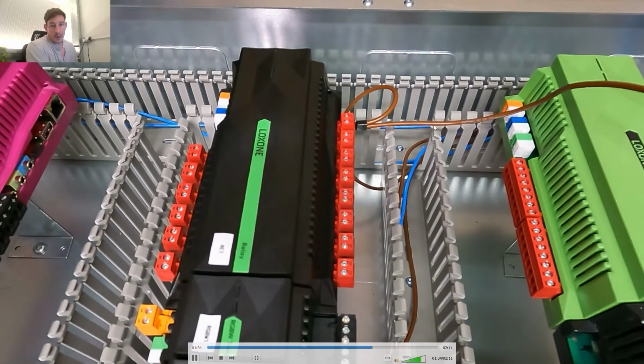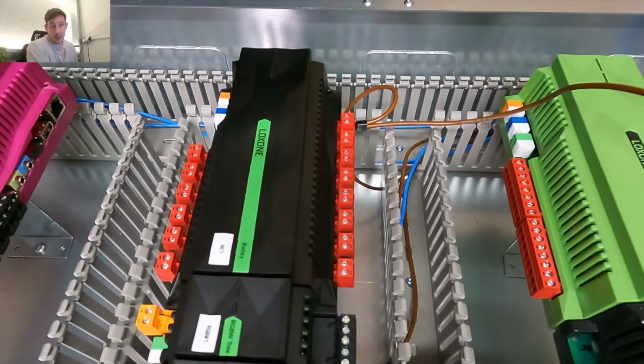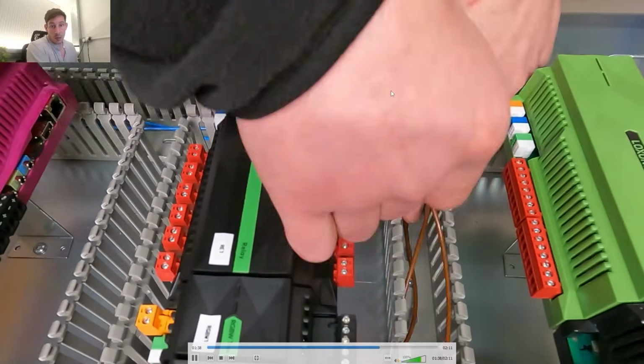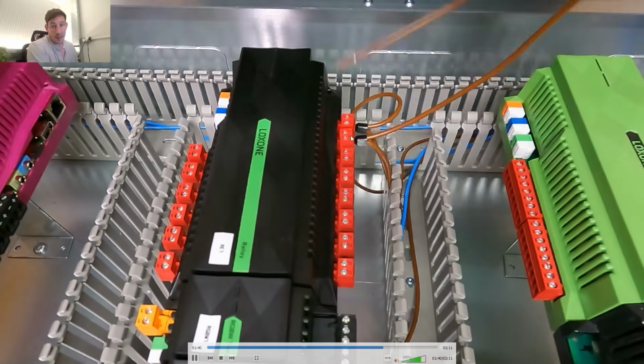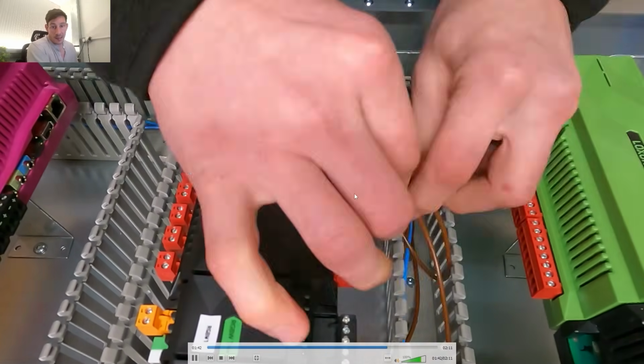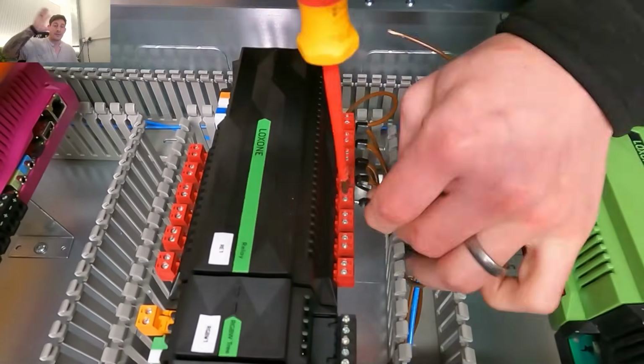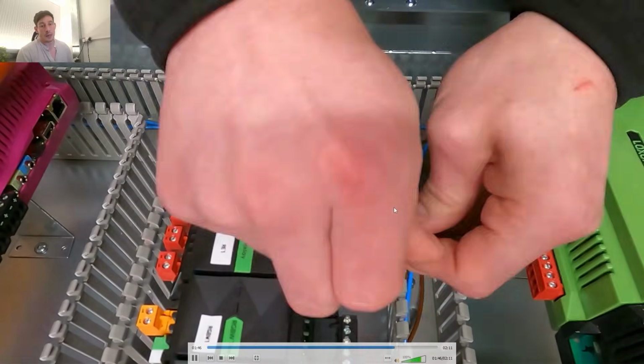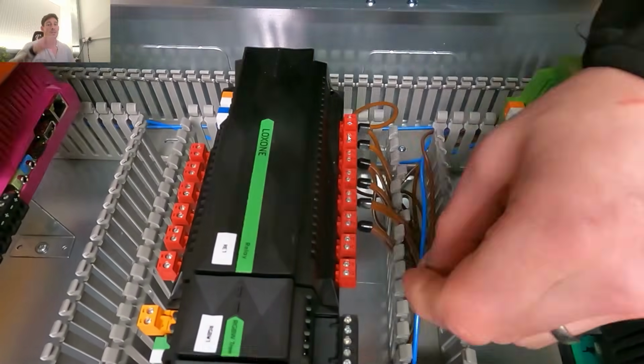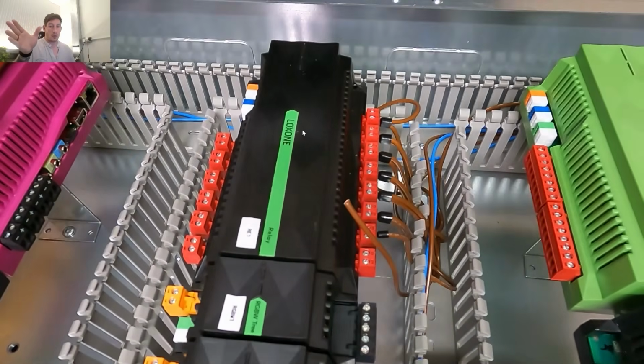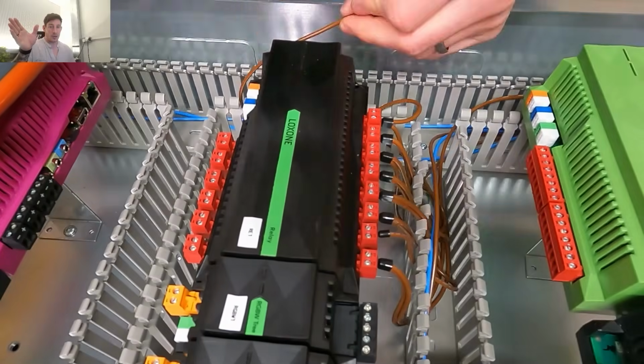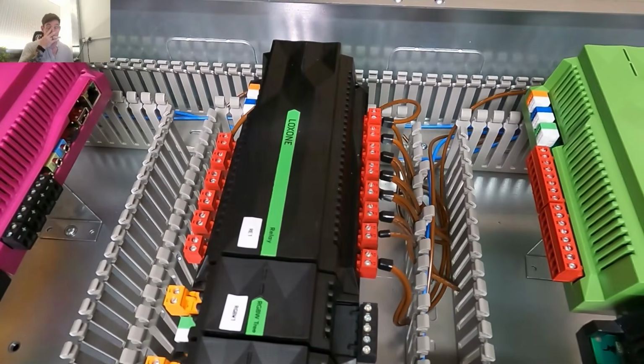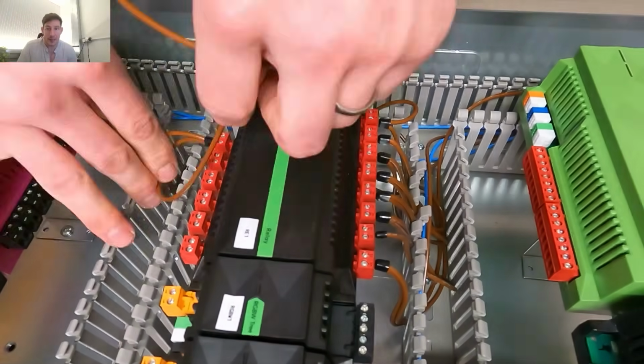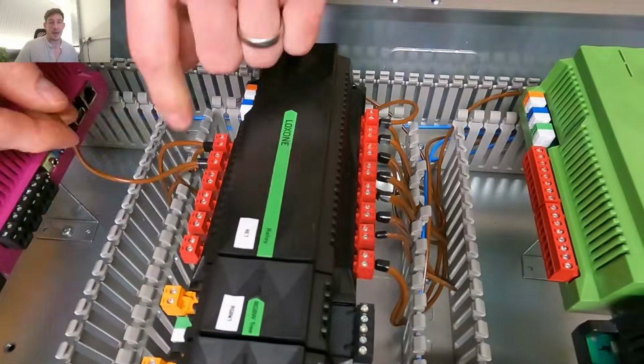So feed coming in, and then we're doubling up, double ferrule, and feeding the next relay, and the next relay, and the next relay. This is just the feed coming from that RCBO being distributed across the feed side of these relays. Then we can program this relay extension to switch based on the application and the spec.